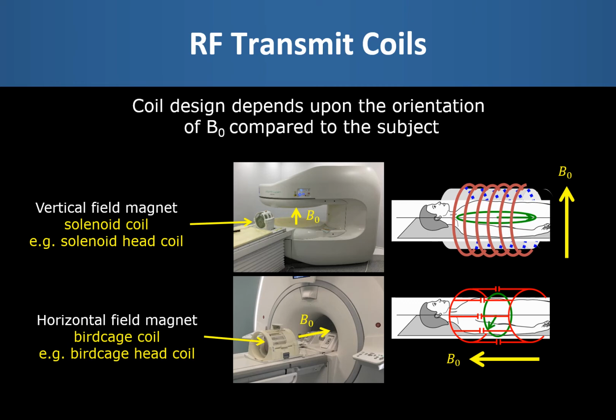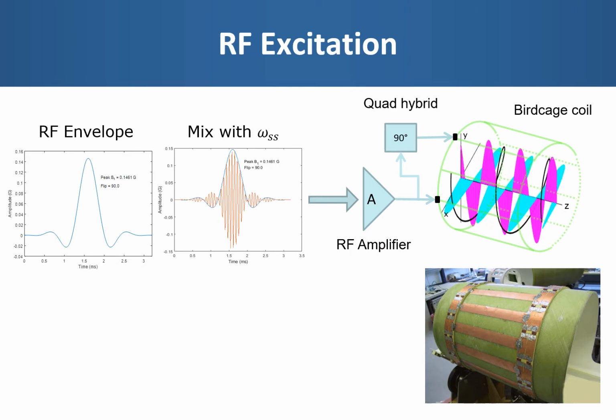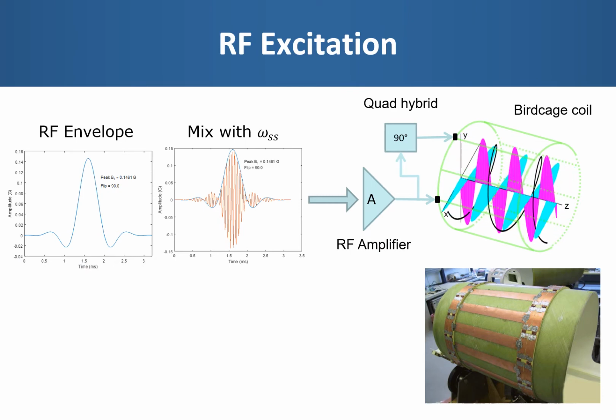Looking at the radio frequency side of things, the design of the transmit coil depends very much on the orientation of B0 compared to the subject. Remember that B1 needs to be orthogonal to B0. For example, if we have this vertical field system, then we can generate the rotating B1 field using a solenoidal coil. Whereas in a horizontal field superconducting magnet, where the coil is in the same plane as the patient, we need to generate our rotating B1 field using a so-called birdcage coil. This is the RF excitation arrangement for a birdcage coil inside a superconducting magnet.